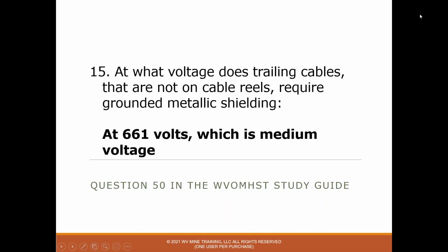15, at what voltage do trailing cables that are not on cable reels require grounded metallic shielding? And that's at 661 volts, which is medium voltage. So your cable going to your continuous miner is probably 995 volts, and it has to have metallic shielding tape around the phases. For medium voltage equipment, this is a safety feature in the cable, because if this cable would get a hole in it and somebody run over it or whatever, that electricity from that phase will encounter that metallic shielding before it can reach the outside. And when that voltage encounters that metallic shielding, a breaker will kick. So that's a very good safety feature for medium voltage cables.